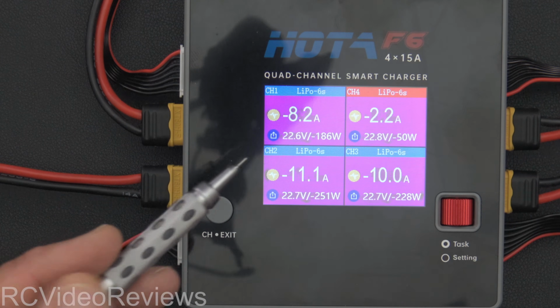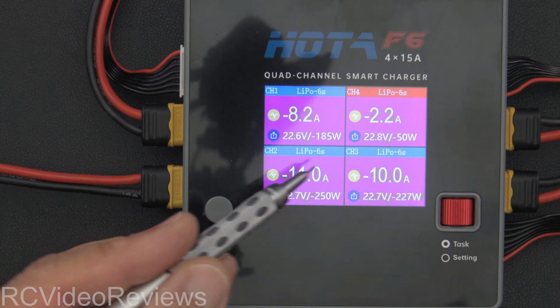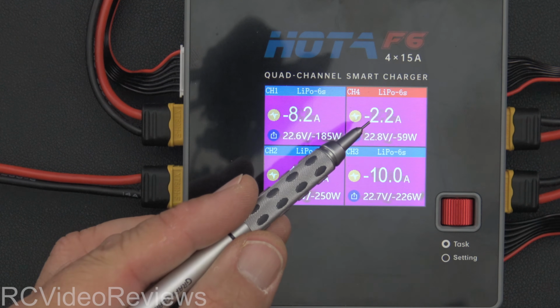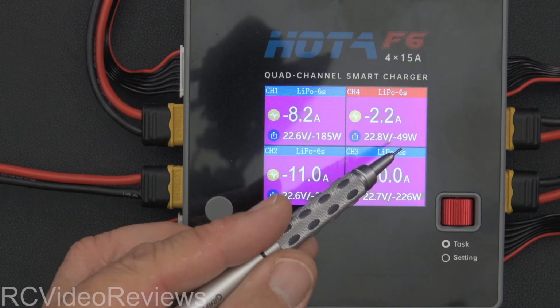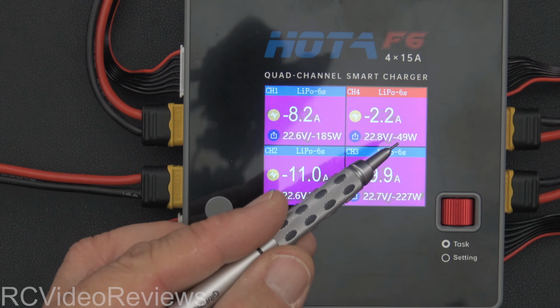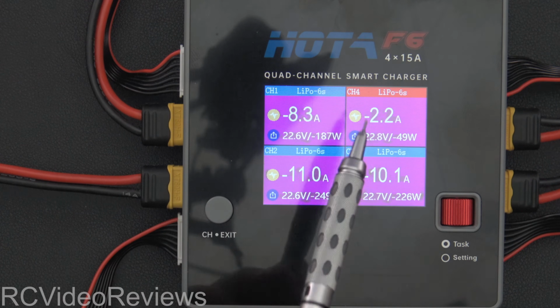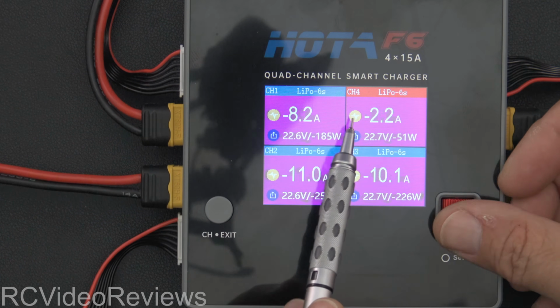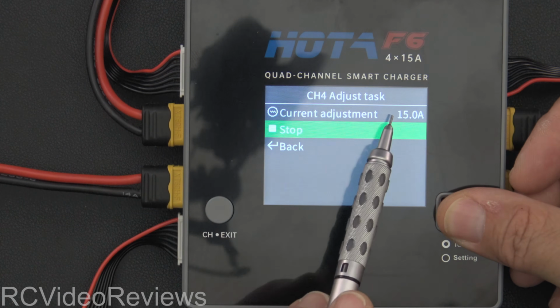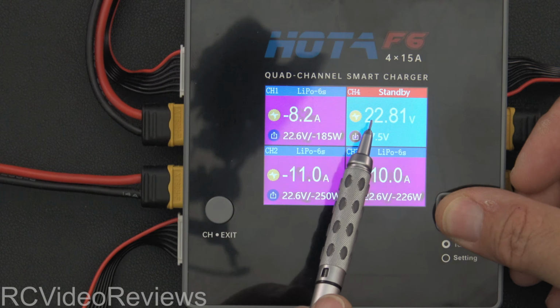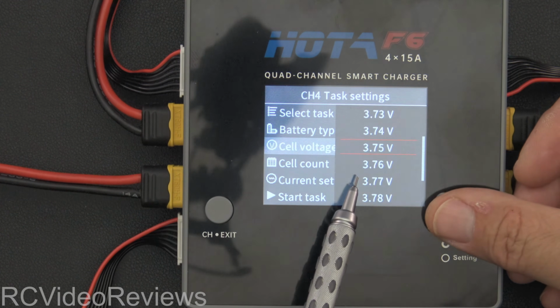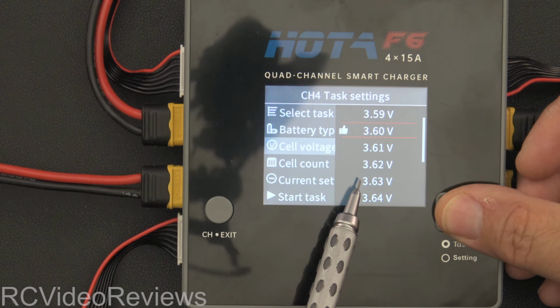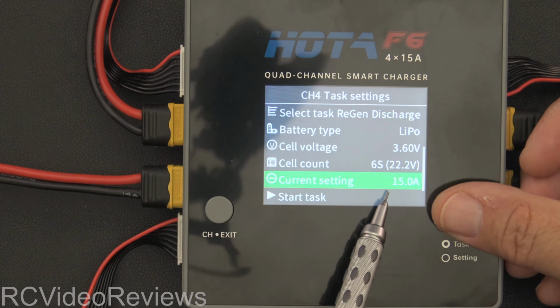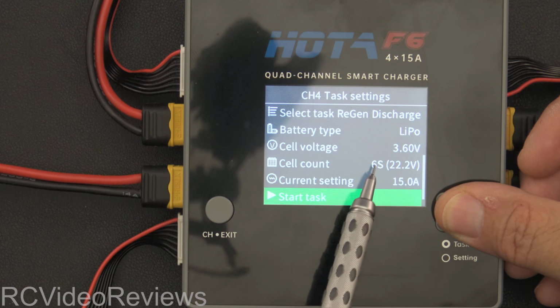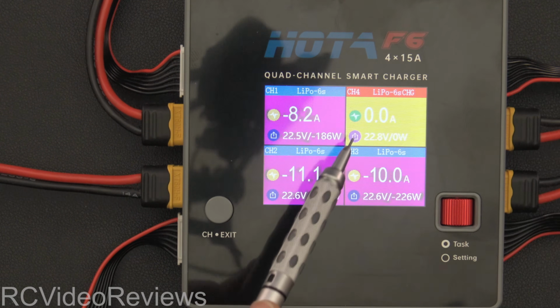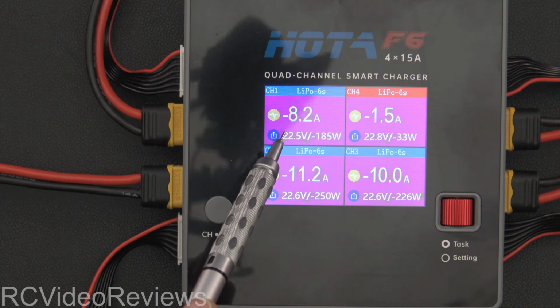So there we go. Now we're doing a regen discharge, and you can see we're at 8.2 on this guy, 11, 10, 2.2. I don't know why that's at 2.2. That's only showing a negative 49 watts. I can assure you guys it will do it because I tested it and I saw a picture. I'm not sure why I'm seeing that. It says 15 amps. And let's see. Let me bring the voltage down a little bit lower just to see. We'll bring it down to 3.6. And we're looking for 15 amps. Yeah, that should do it. Regen 3.6, 15 amps. We should see that climb all the way up to 10.